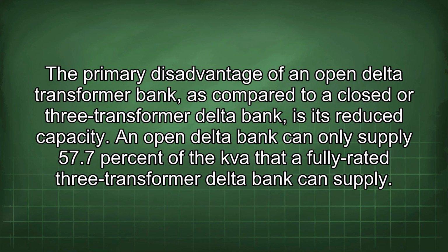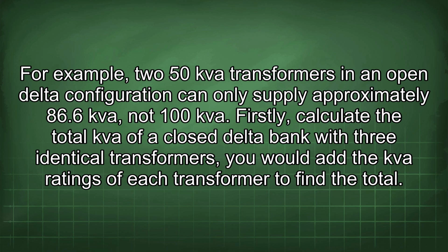The primary disadvantage of an open delta transformer bank, as compared to a closed or 3 transformer delta bank, is its reduced capacity. An open delta bank can only supply 57.7% of the kVA that a fully rated 3 transformer delta bank can supply. For example, two 50 kVA transformers in an open delta configuration can only supply approximately 86.6 kVA, not 100 kVA.